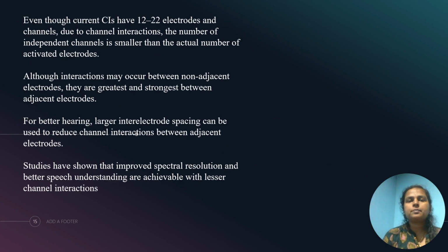Even though current cochlear implants have 12 to 22 electrodes and channels, due to channel interaction, the number of independent channels is smaller than the actual number of electrodes. Although interactions may occur between non-adjacent electrodes, they are greatest and strongest between adjacent electrodes. And for better hearing, a larger inter-electrode spacing can be used to reduce channel interactions between adjacent electrodes. The improved spectral resolution and better speech understanding are achievable with lesser spacing, lesser channel interaction.